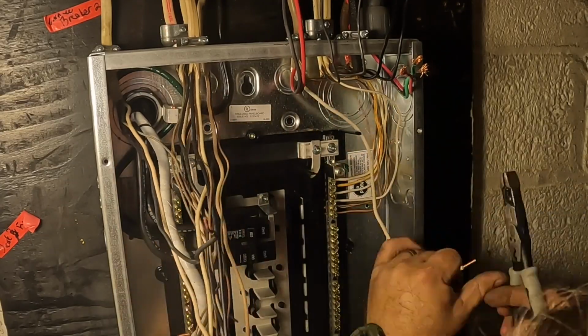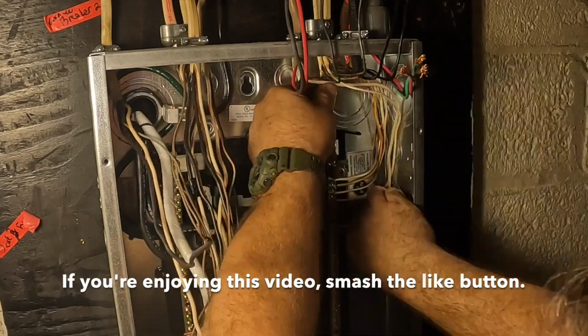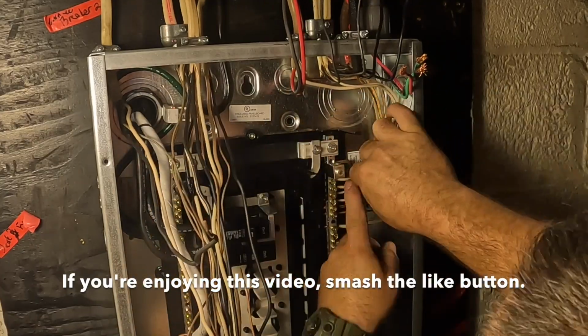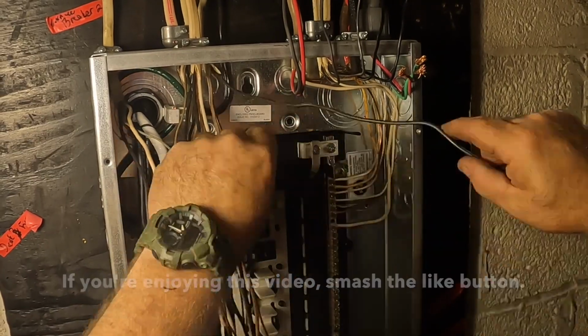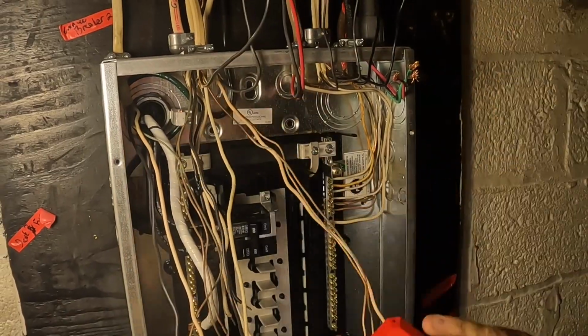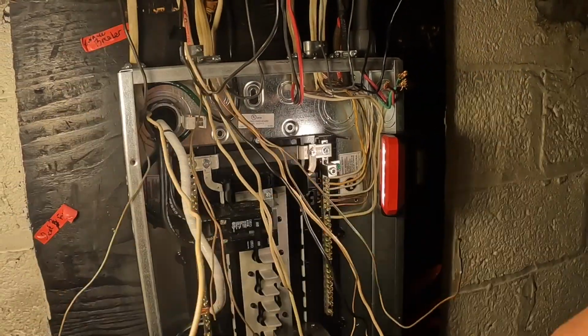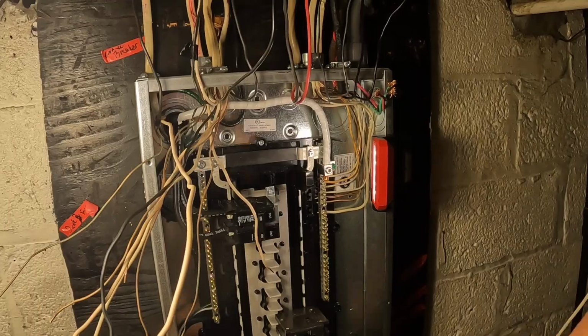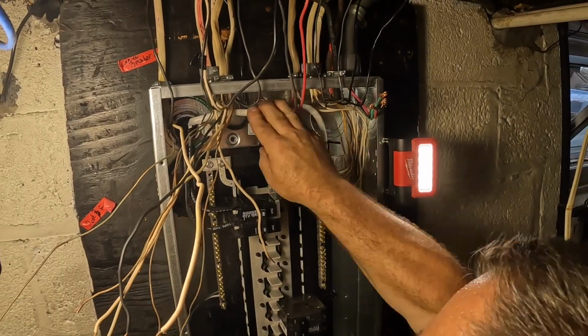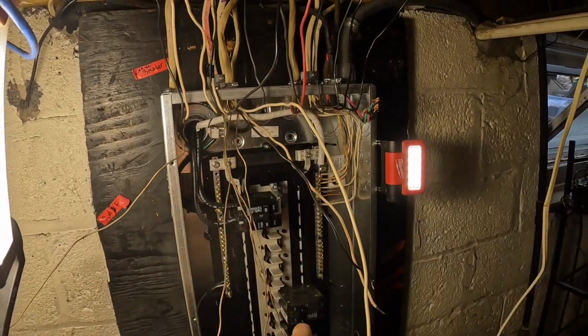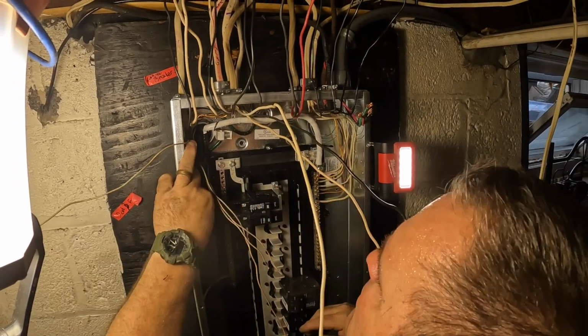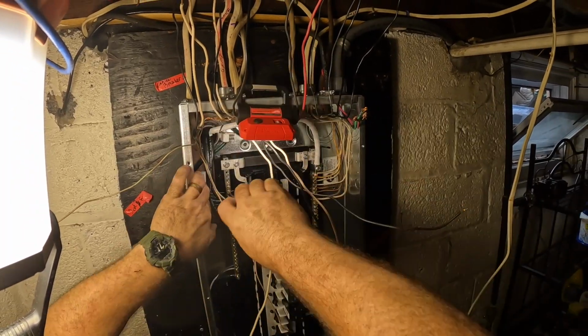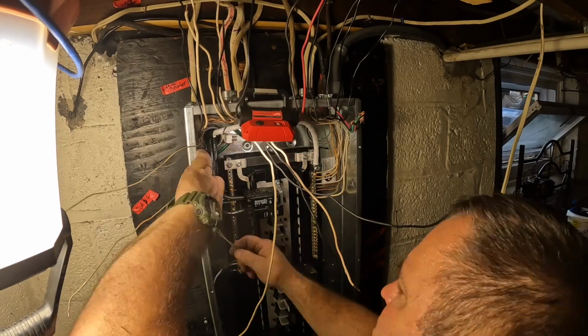So being that this is a main breaker panel, all my grounds and neutrals are bonded, and right above where I'm working, right there behind the lug, I don't know if you can see it, is that green screw, and that's the main bonding jumper. It's a screw, and what that does is that bonds the neutrals to the enclosure, forming a bond between the enclosure and the neutral so that everything's properly grounded and connected to earth.